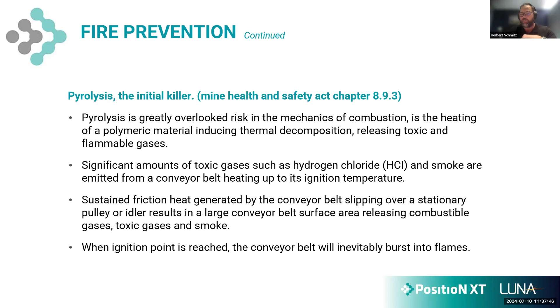Now, then we really have to look at what happens within that process of pyrolysis. As I said, with the belt slipping over a stationary pulley at roughly 180 degrees Celsius friction surface temperature, the rubber starts converting into a gaseous state, releasing very toxic gases such as hydrogen fluoride, phosgene, bromide, depending on the type of conveyor. And now, the more flame resistant or flame retardant the conveyor belts used in mining, the higher the toxicity of these conveyance systems. Bringing us back to earliest possible thermal detection.